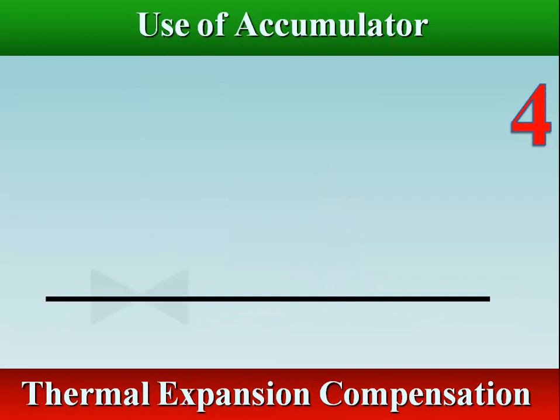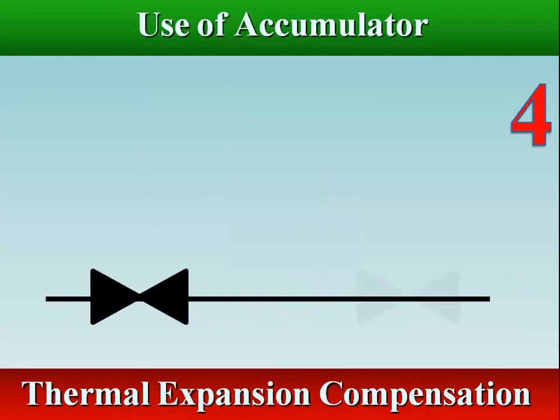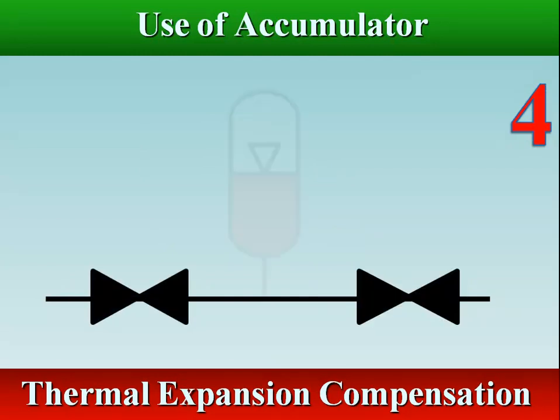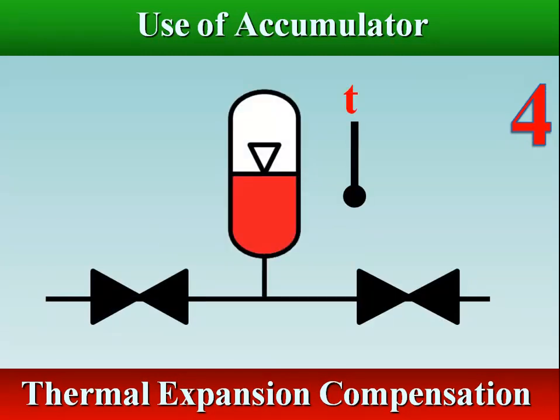Changes in the volume of a liquid resulting from changes in the temperature within a closed circuit can increase or decrease the internal pressure. An accumulator can be used to mitigate any such fluctuations in the pressure.